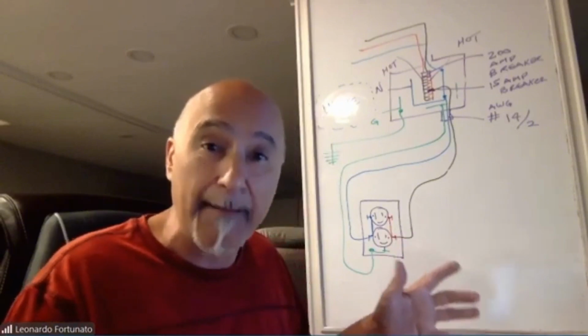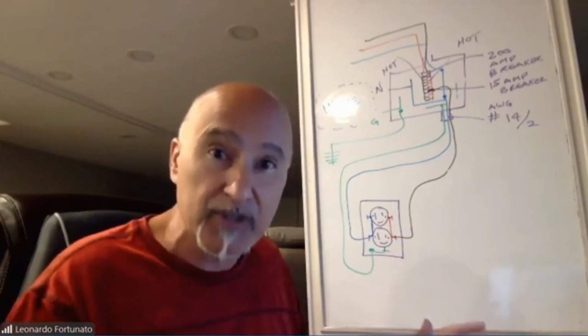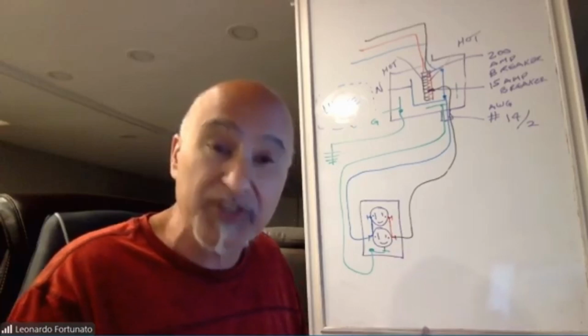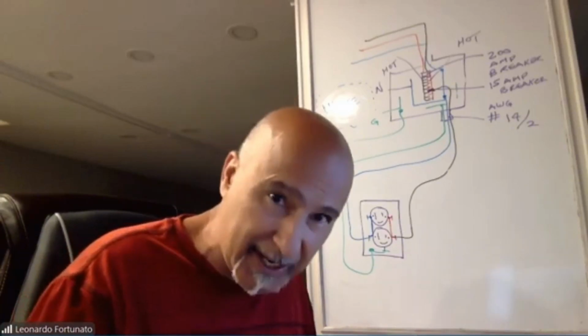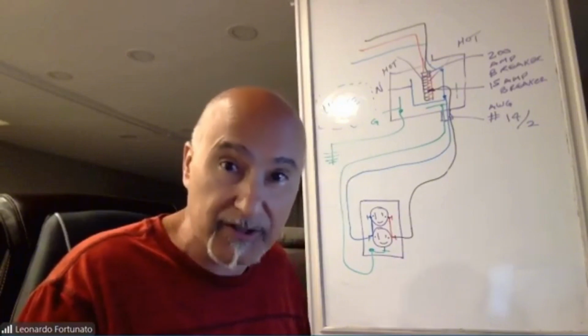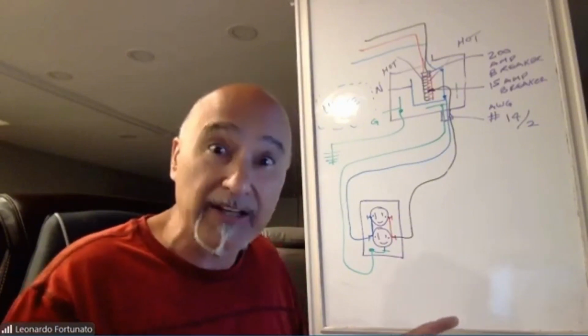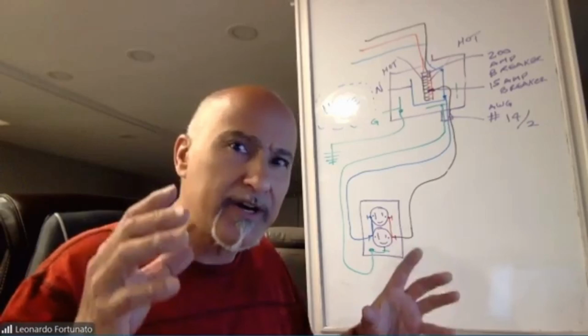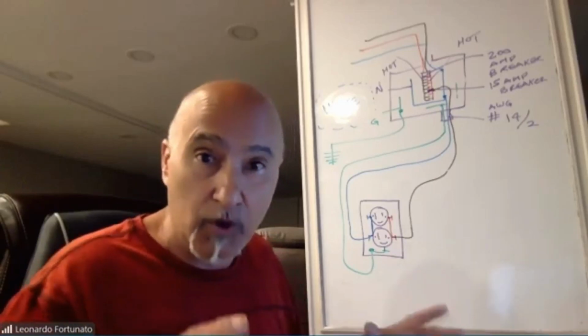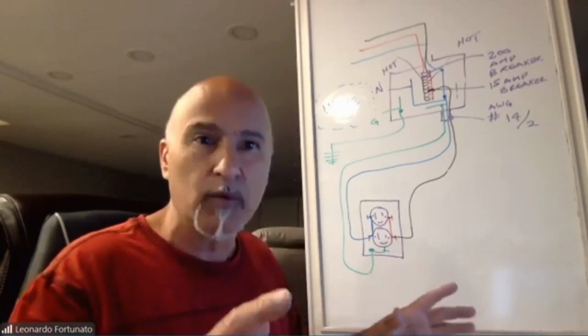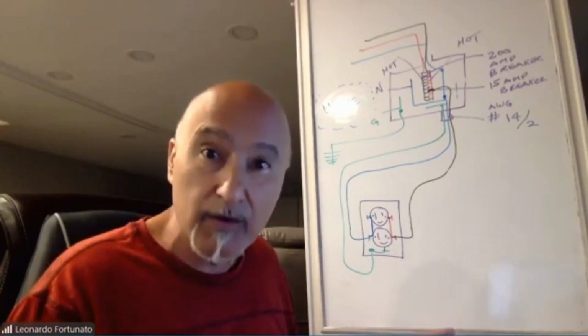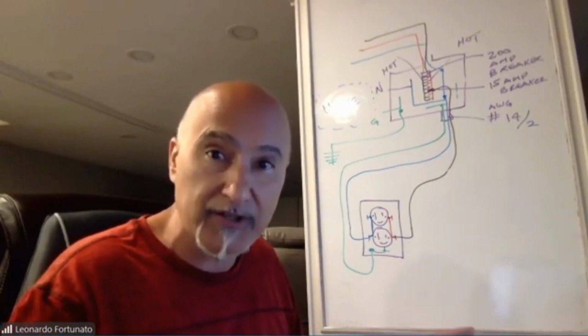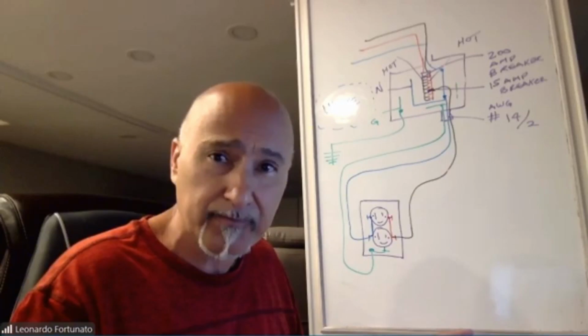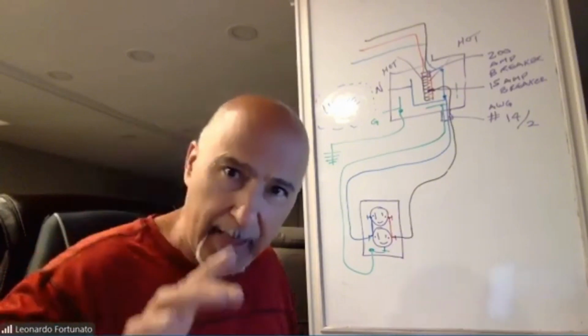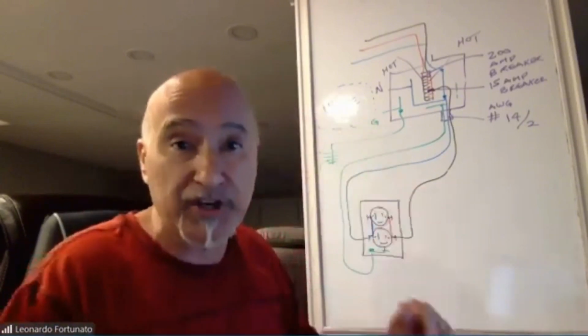For example, a 15 amp circuit is going to be 15 amps times 120 volts, which tells us we have a total capacity of 1800 watts. We want to be proactive, so what we put on that circuit, we only want to use 80% of that capacity, which is 1440 watts. That way, at any given time, if somebody were to overload a circuit, we have a little buffer before the power actually goes off.